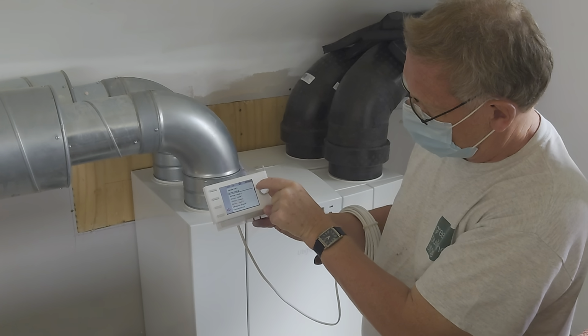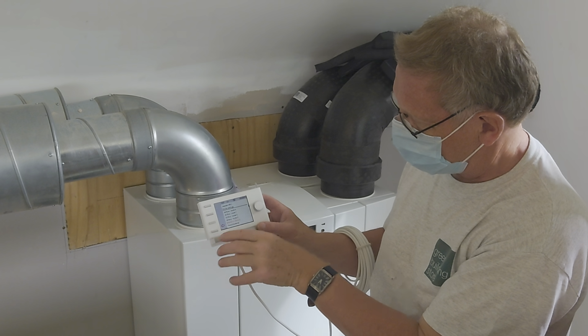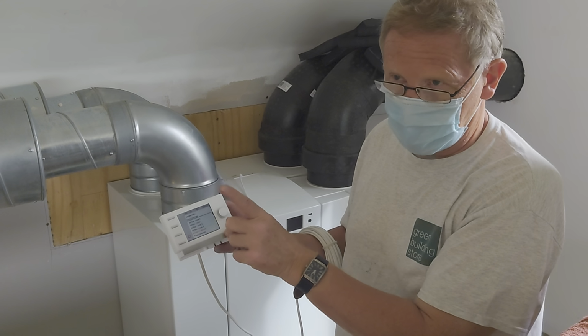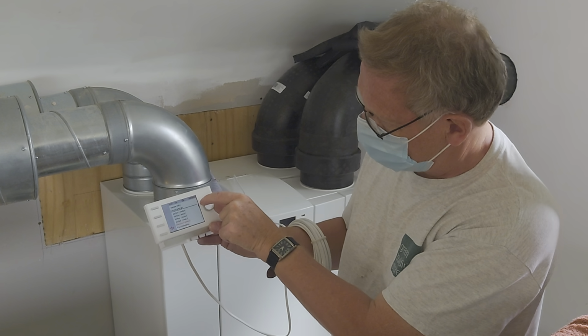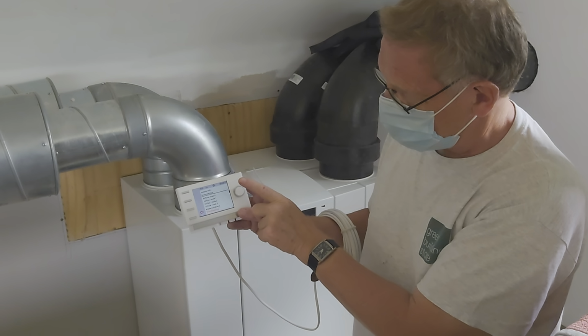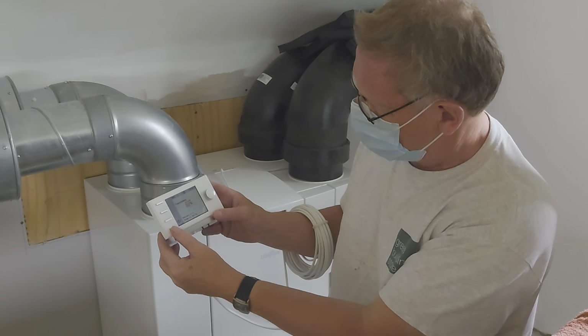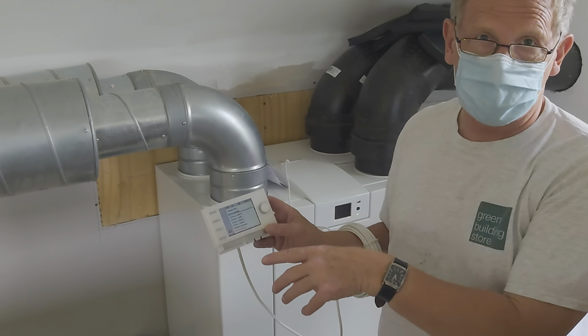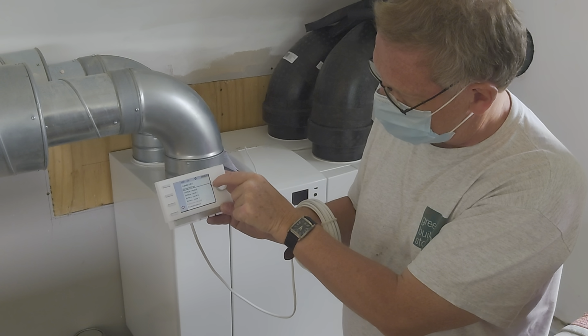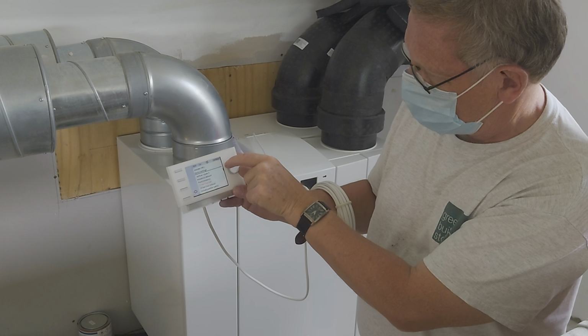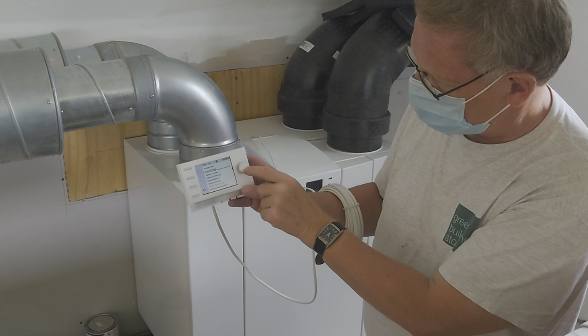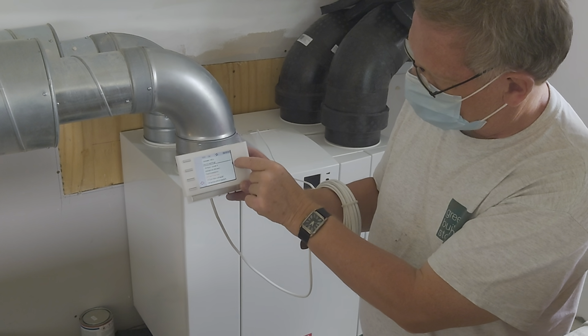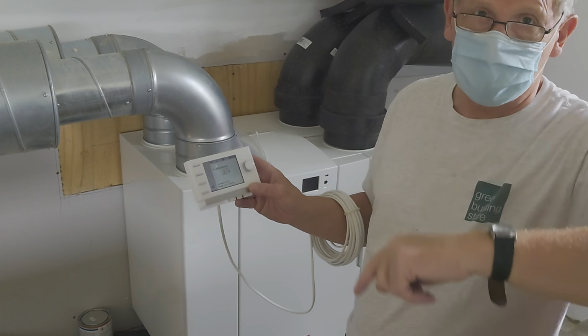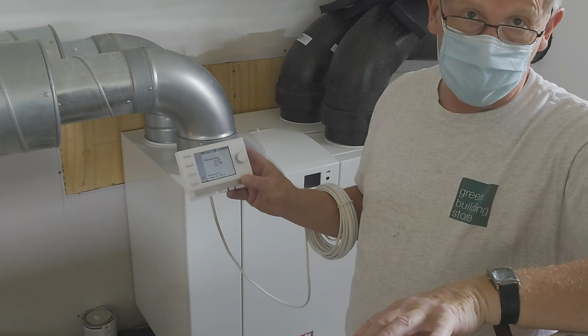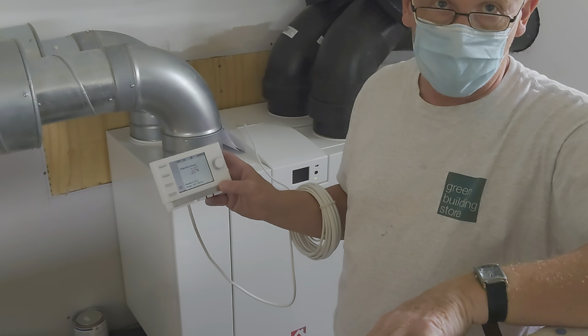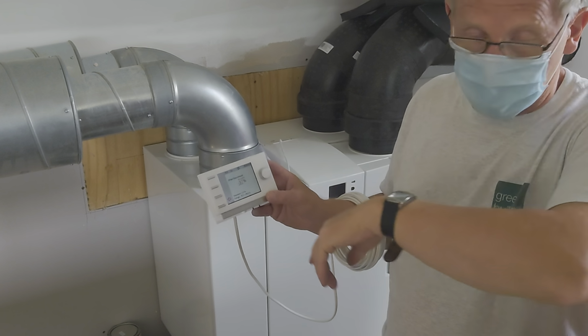So those are airflows. Imbalance is a commissioning setting. It allows me to put the fans slightly out of balance with each other if I wanted to. And I have done to a small degree. Fixed imbalance, I think, allows you to, if we thought the fans were underperforming, I can compensate using that. I haven't had to. Offset flow inlet and offset flow exhaust. The inlet is 0 and the exhaust is minus 3.7%. When I was commissioning it, I wanted to get the two fans in balance with each other. They were slightly out of balance, so I had to drop the extract fan speed by 3.7% to get them in balance.